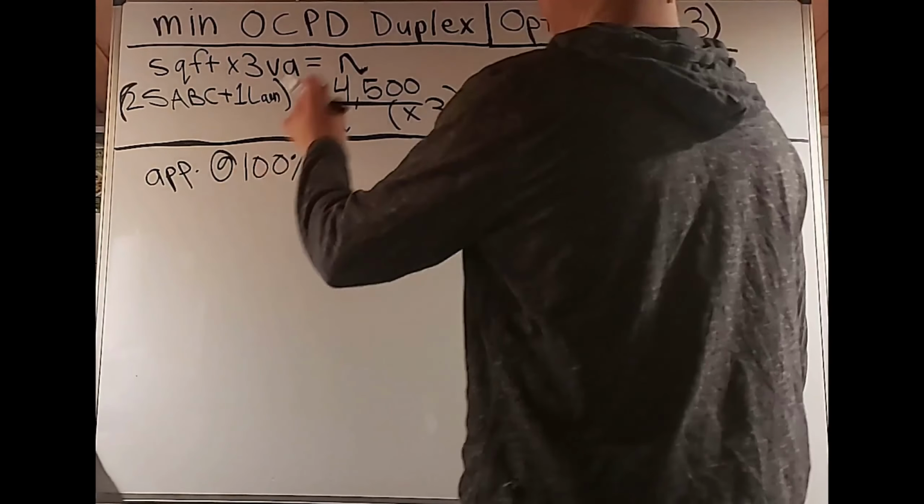If it doesn't tell us the nameplate rating, then we're going to go into table 220.55, and we're going to see column C. We're going to rate it as one appliance at 8 kilowatts, and then we're going to multiply it by 3 units and get 24 kilowatts for our rating. So in other words, if we're using the optional method and it doesn't say a nameplate rating for range, we're going to have 24 kilowatts.